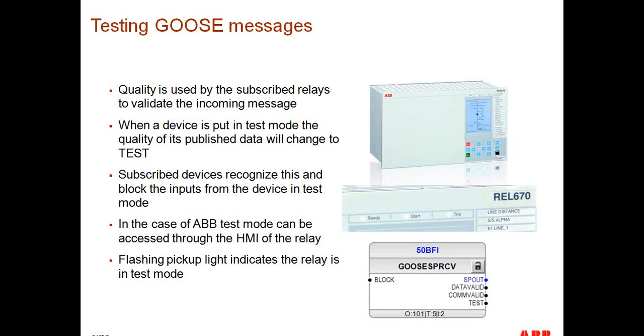And just getting down into a little bit of the nitty-gritty details, in the case of the Relion relays, the receiving block can actually provide four types of information. The first one is the actual status of the binary point that's being sent, whether it's a 1 or a 0. Then we can say whether the data is valid or not. Then we can say whether the communication is valid or not. And then we can also indicate whether the message that's being received is in test mode or not. And then these variables can in turn be used internally in the relay for different purposes.